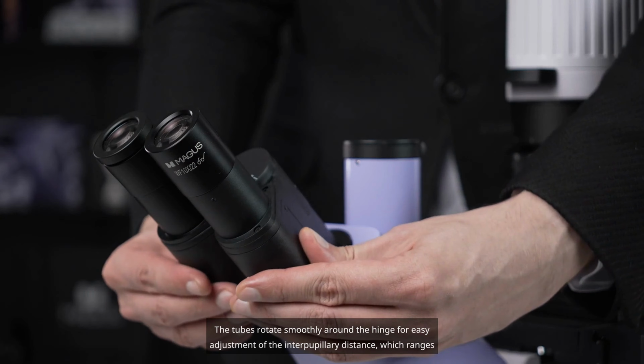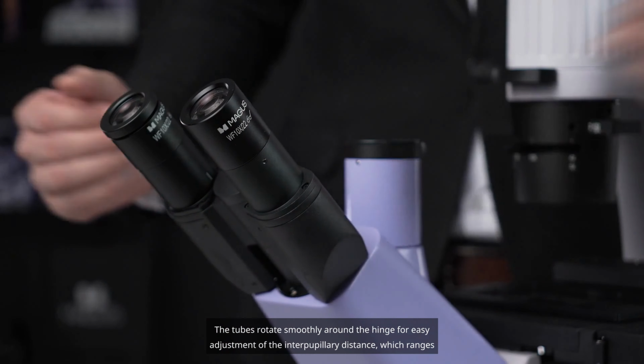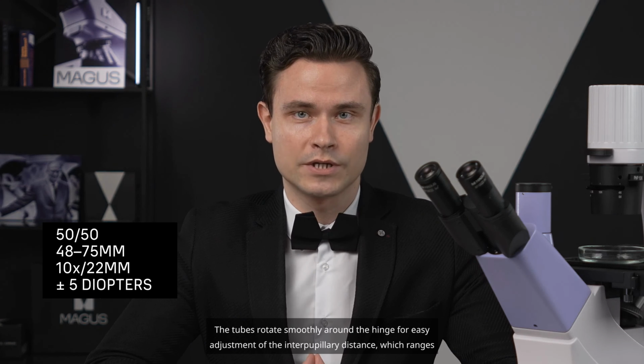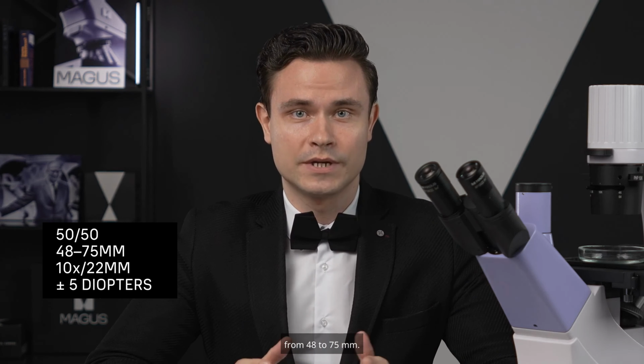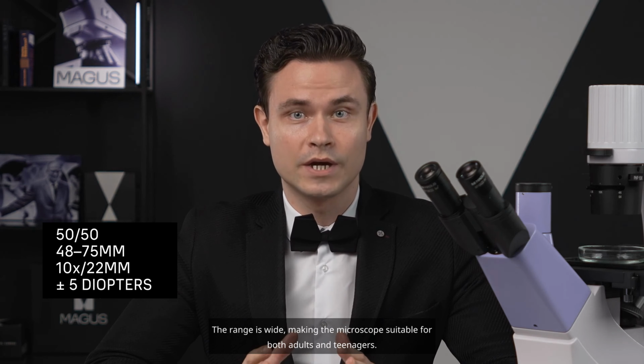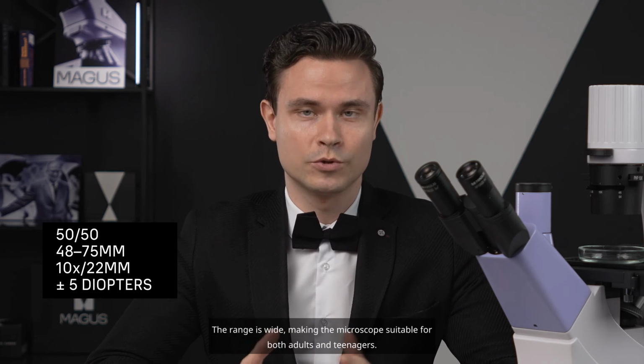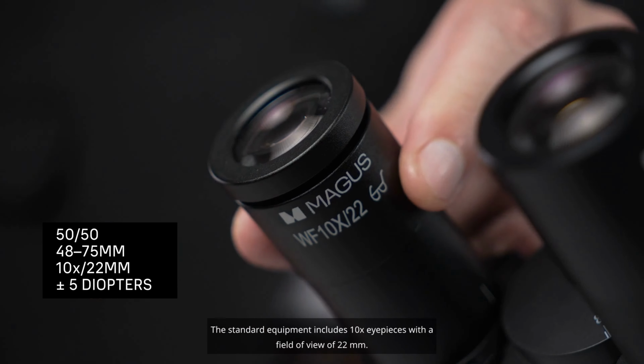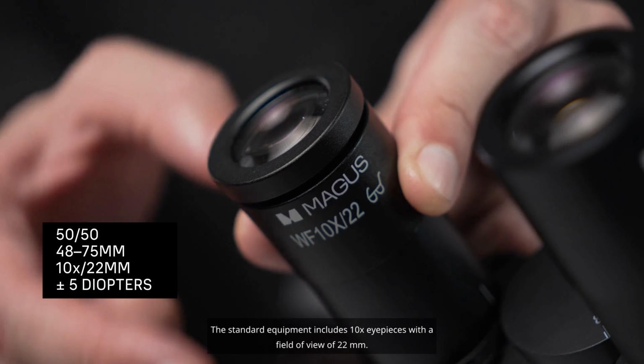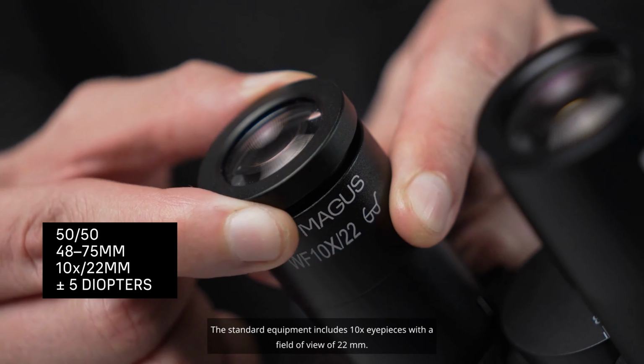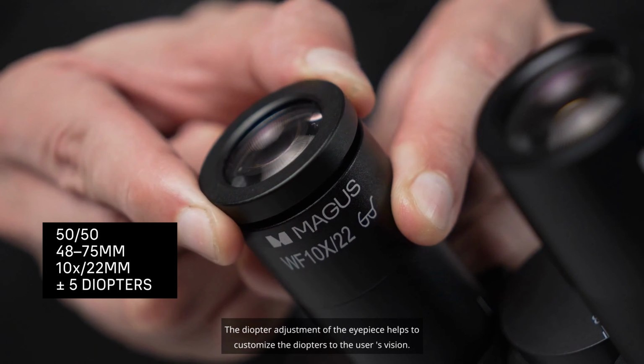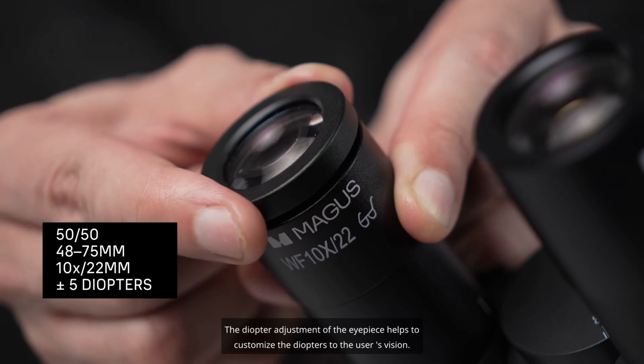The tubes rotate smoothly around the hinge for easy adjustment of the interpupillary distance, which ranges from 48 to 75 mm. The range is wide, making the microscope suitable for both adults and teenagers. The standard equipment includes 10x eyepieces with a field of view of 22 mm. The diopter adjustment of the eyepiece helps to customize the diopters to the user's vision.